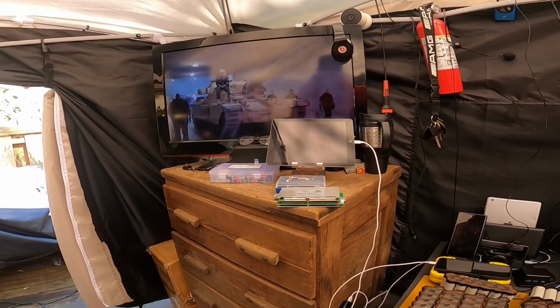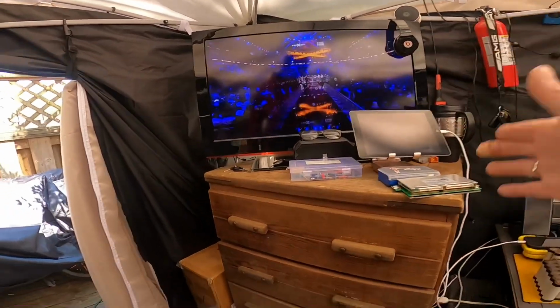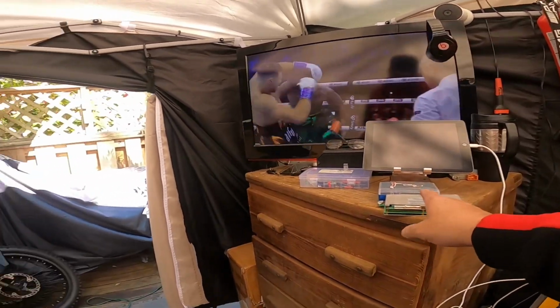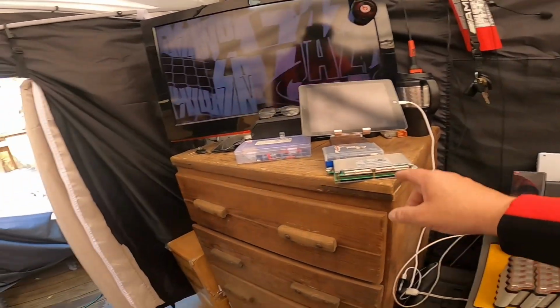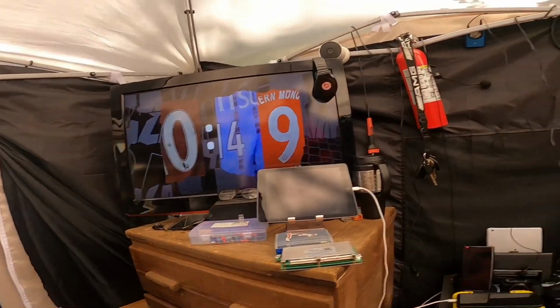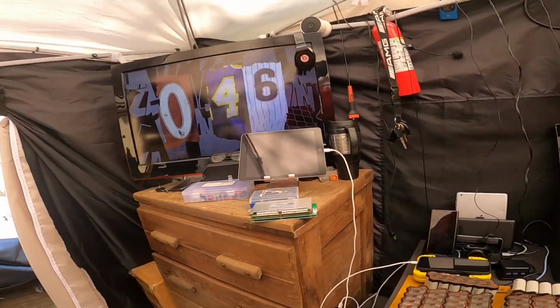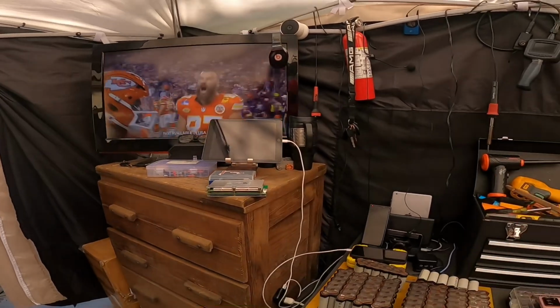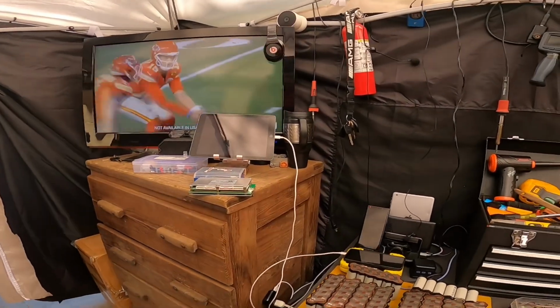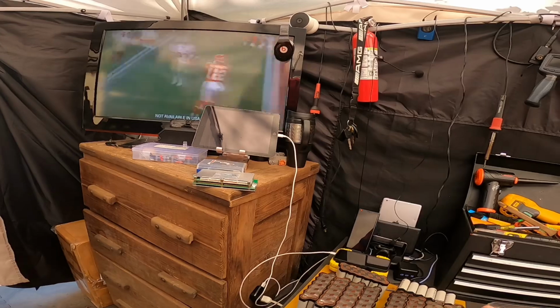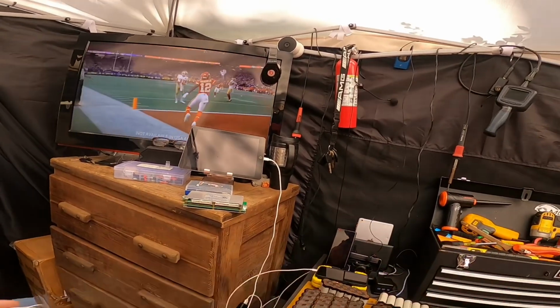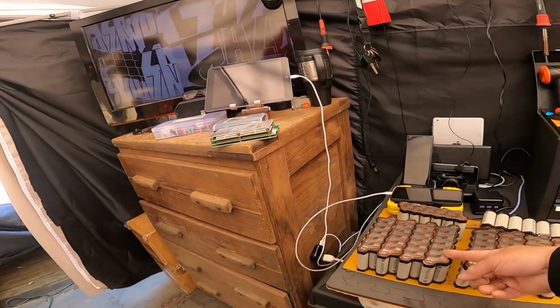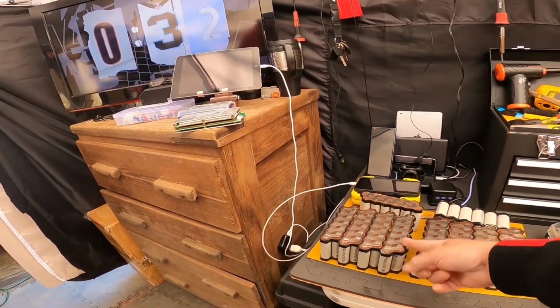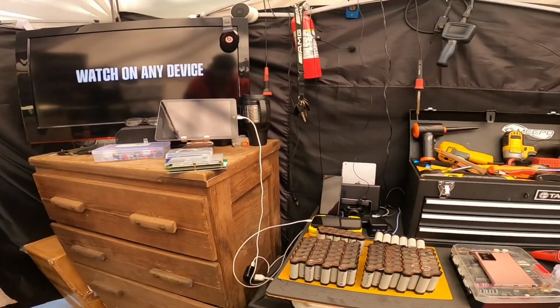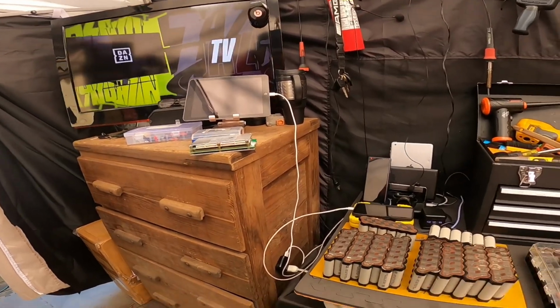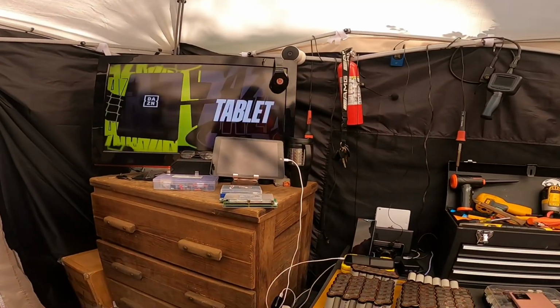And then at that point, if you open up your pack, you could go through with the meter, measure the voltages at each stage, and determine which stage has the issue. The BMS is just doing that diagnostic for you. So yeah, it's diagnosing. However, it cannot repair, regardless. If the BMS sees an issue in one of those stages, it cannot repair the issue. Now, like I said, it will attempt to balance different offset voltages over long periods of time, but if there's a broken connection, bad cells, whatever, it can't magically repair that fault. Just making you aware of it.